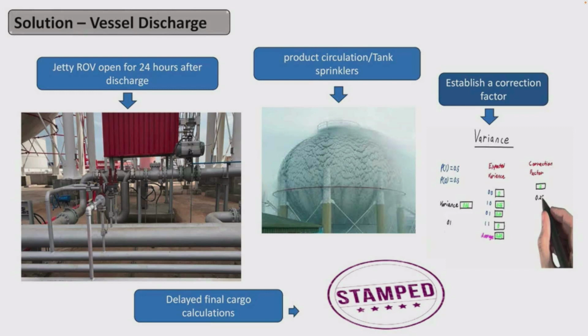If you shut down the ROV, you're restricting the space between the ROV, the flow meter, and the NRV, which isn't much. You have some liquid trapped inside your flow meter, and then a vapor phase immediately after, and you close this vapor phase. Definitely some vapor will slip in, and your mass flow meter will show movement at the jetty. That's for the flow meter. We leave it 24 hours, and after 24 hours, you close it.